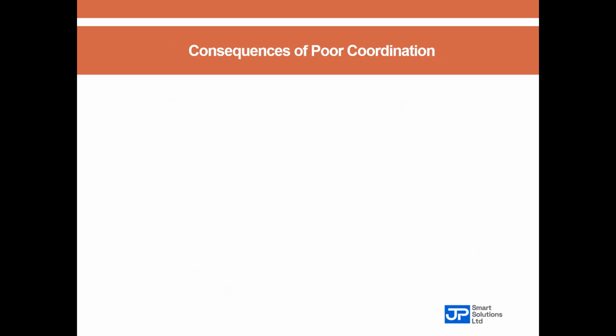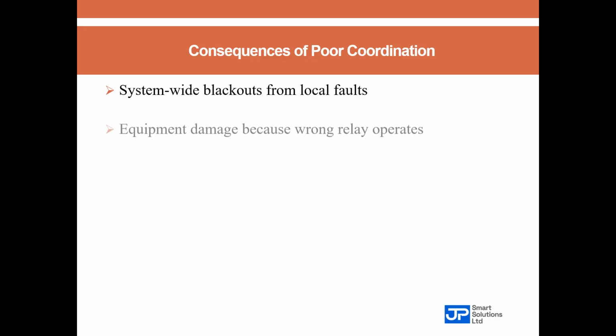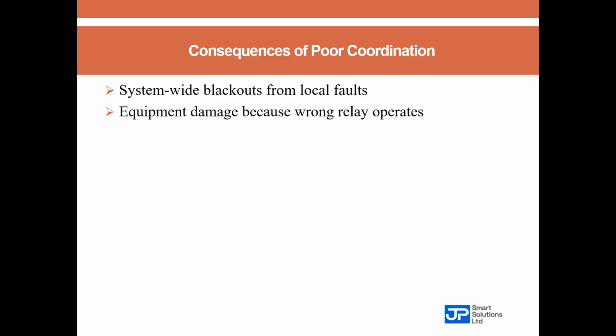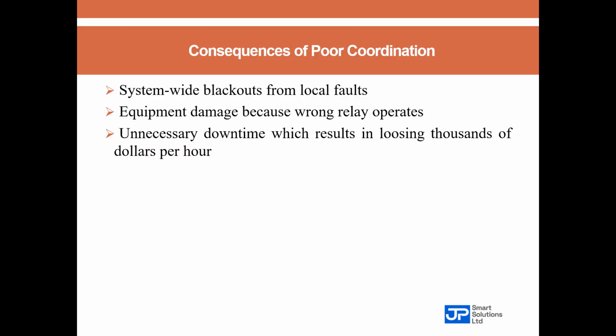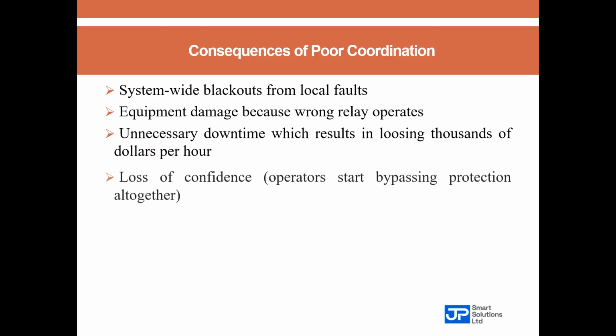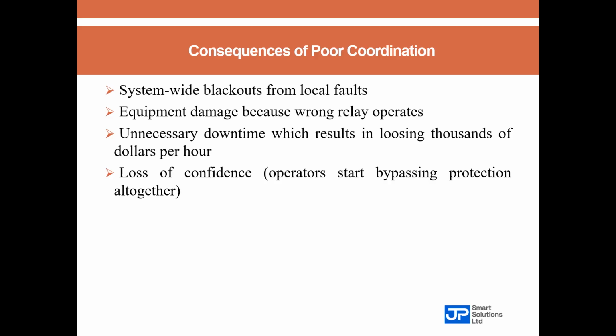Consequences of poor coordination. Poor coordination leads to system-wide blackouts from local faults. It leads to equipment damage because the wrong relay operates. It leads to unnecessary downtime, which results in losing thousands of dollars per hour. Remember, profit is very important. Then it also results in loss of confidence, because if your protection scheme is not adequate, not properly coordinated, operators start bypassing your protection altogether, because you're having nuisance tripping.